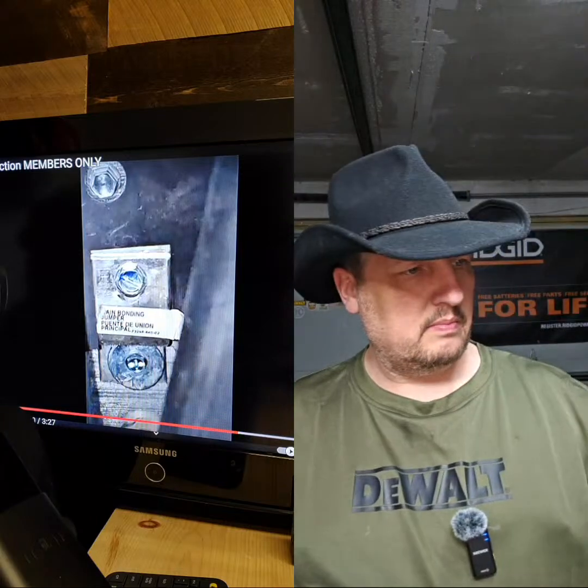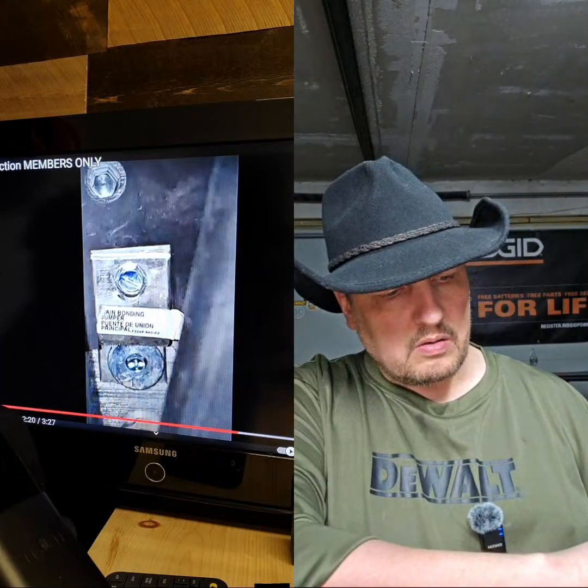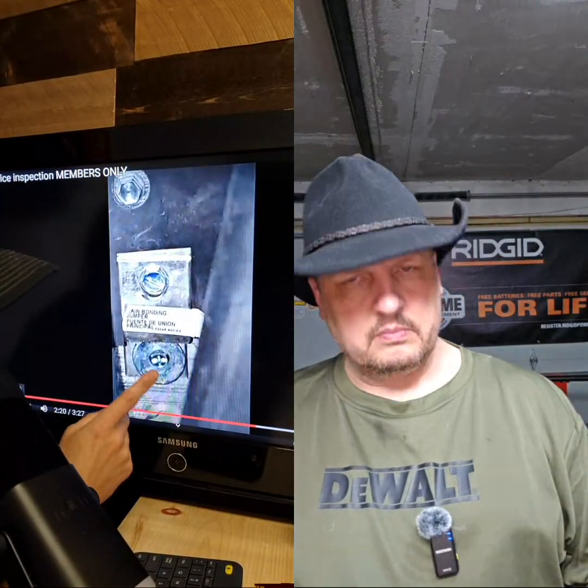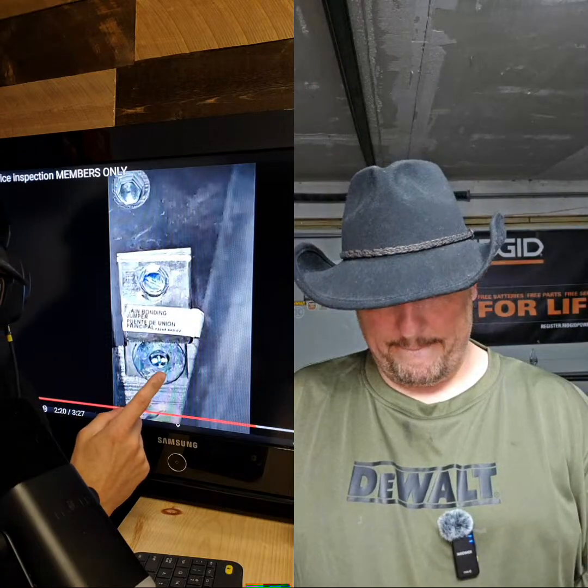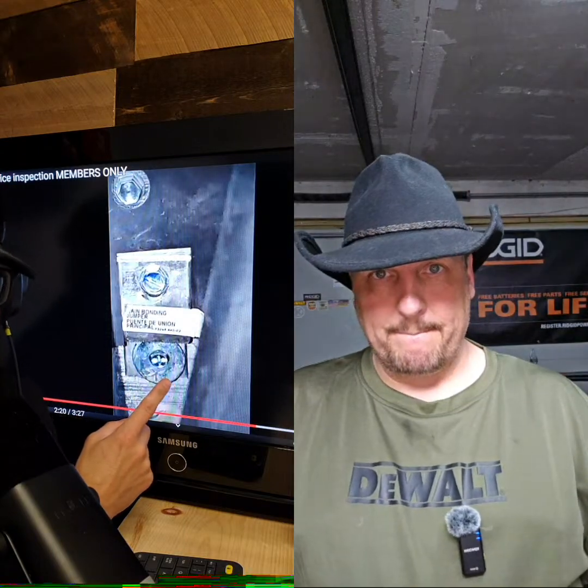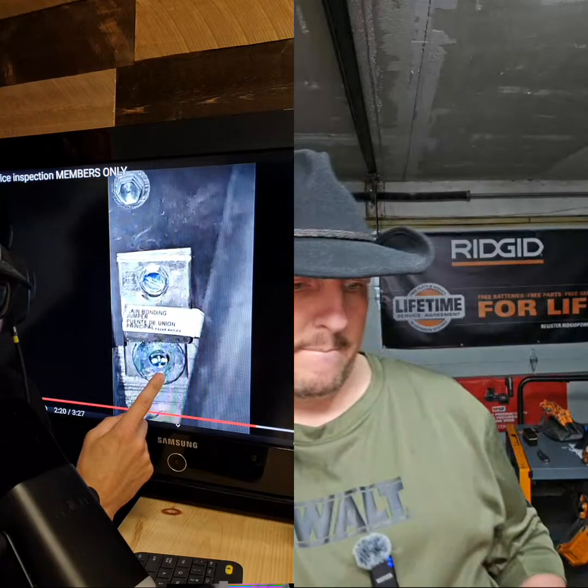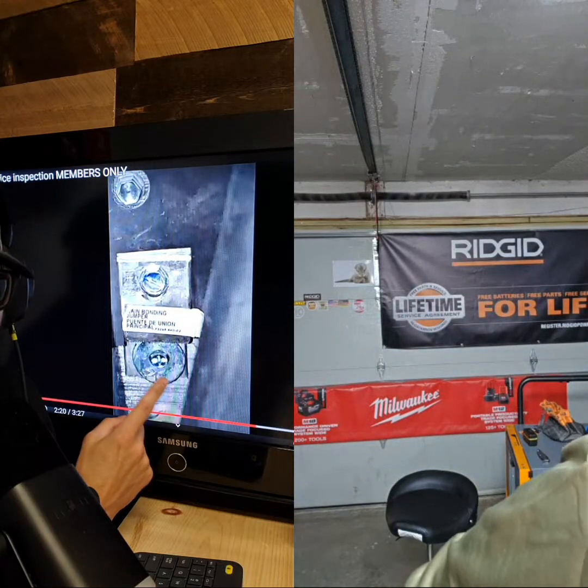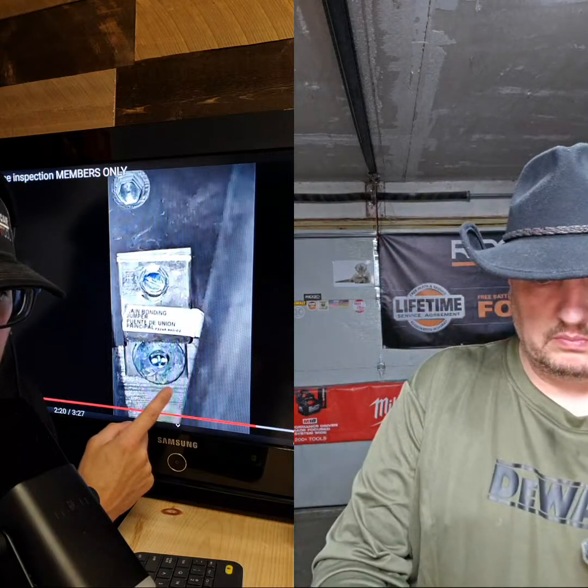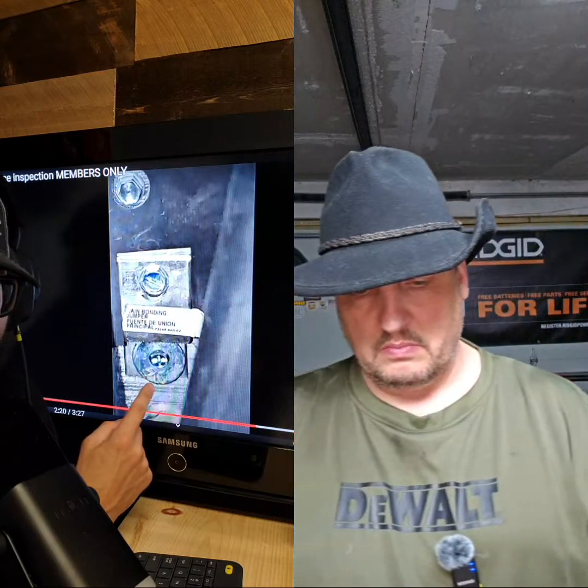Does it need to be a single point to prevent ground looping? Yeah, exactly, exactly, so this thing needs to go. Also, the problem with this is it will cause ground looping, and this is guaranteed to carry current now because we've bonded the grounds and neutrals at the sub. So now we're dividing our current in half on the neutral, half on the ground.